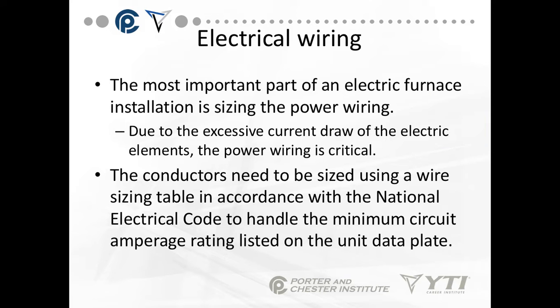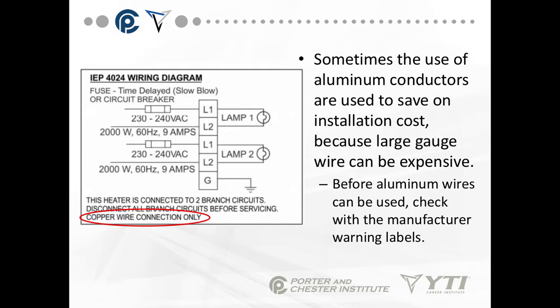The most important part of an electric furnace installation is sizing the power wiring. Due to the excessive current draw of electric elements, the power wiring is critical. The conductors need to be sized using the wiring size table in accordance with the NEC, or National Electrical Code, and must handle the minimum circuit amperage listed on the unit data plate. The unit data plate will give you the wiring diagram, the fuse information, and it will tell you copper wire only.